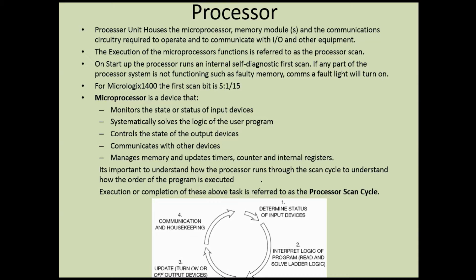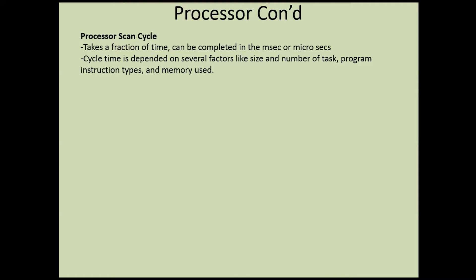Execution or completion of these tasks is referred to as the processor scan cycle. Looking at a picture of the scan cycle: after initial diagnostic testing, step one determines the status of the input devices - it reads all input modules and cards. Step two interprets and solves the logic of the program. Step three updates or turns on or off output devices. Step four communicates with other PLCs or equipment on the network and performs housekeeping.